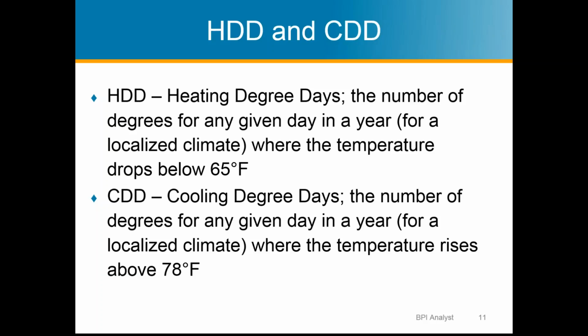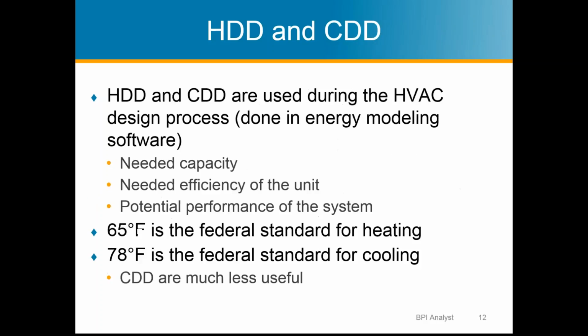Cooling degree days is not as good of a predictor of actual cooling energy required for various reasons, but primarily because a lot of the cooling demand that's required is more about the radiant energy from the sun and not about the ambient air temperature. But heating degree days is a good predictor. And being able to do that simple math is important on your written exam. So just knowing 65 degrees is the heating degree day threshold and 78 is the cooling degree threshold is important to remember.